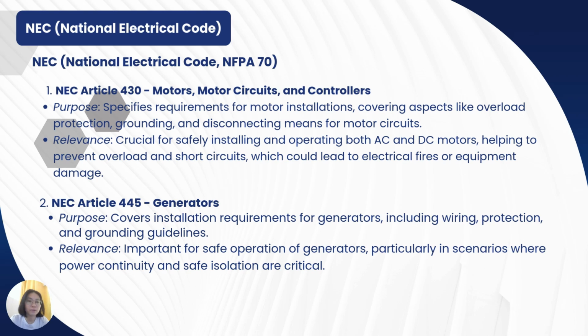installing and operating both AC and DC motors, helping to prevent overload and short circuit, which could lead to electrical fire or equipment damage. Next, NEC Article 445 standard is about generators. The purpose is to cover installation requirements for generators, including wiring, protections, and grounding guidelines. Besides that, this standard is also important for safe operation of generators, particularly in scenarios where power continuity and safe installations are critical. So this is all about the international and national standards for electrical machines.